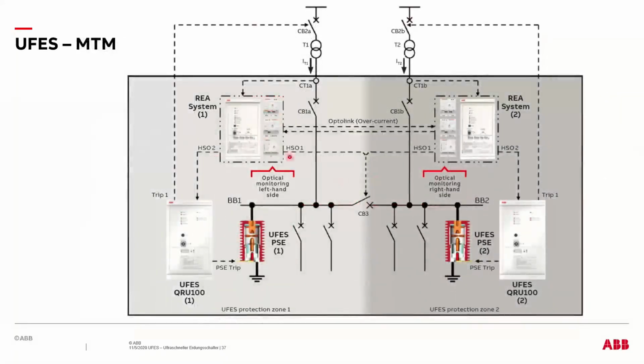Similarly, for a main equipment, it's a similar setup where you have your REA system and the UFES system dedicated for each side, for bus A and bus B, and it's the exact same configuration. And the REA systems on bus A and bus B are going to communicate with each other, depending upon if you have an arcing fault on bus A side or on bus B side, right?